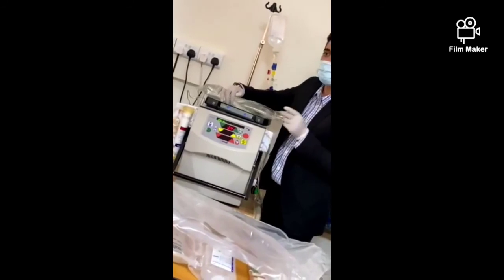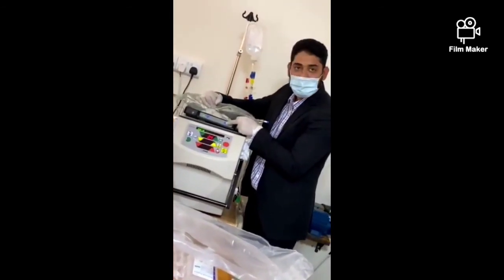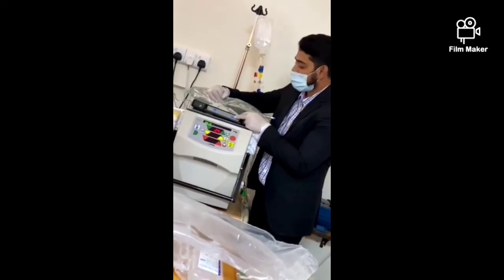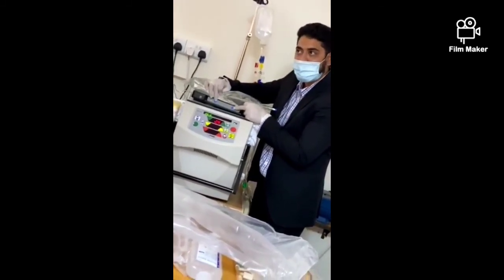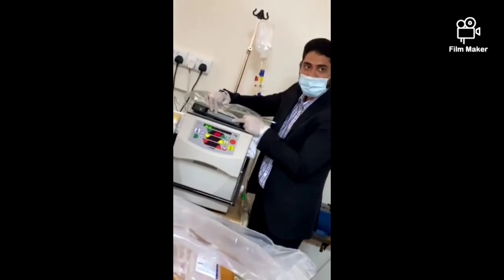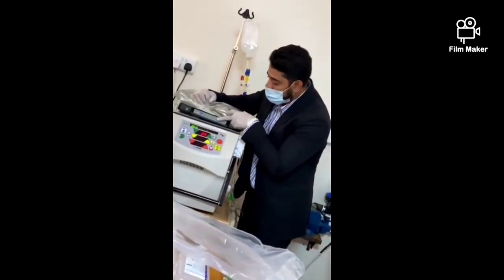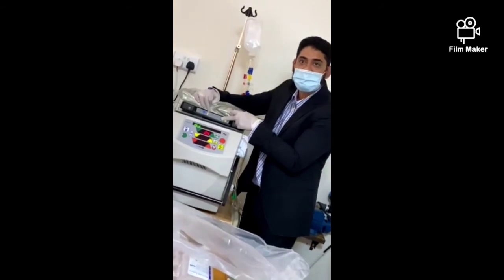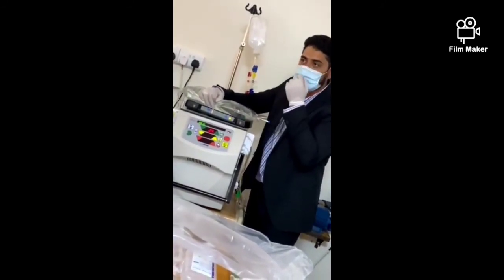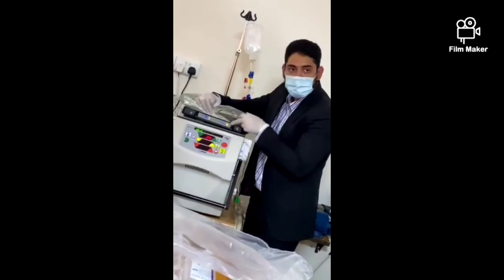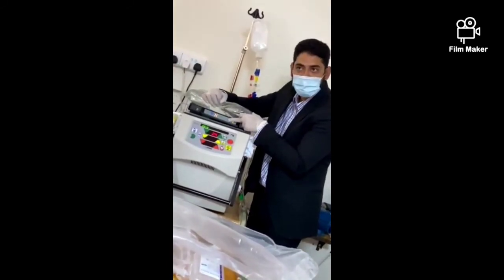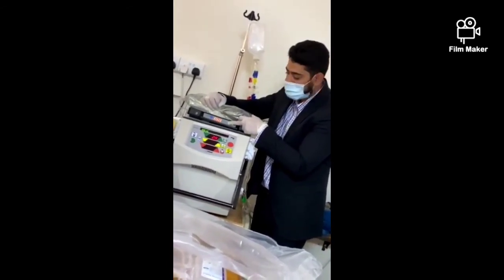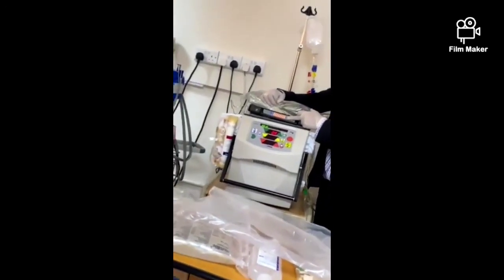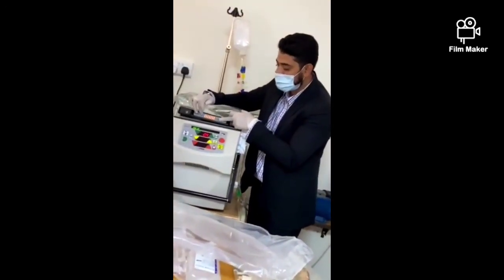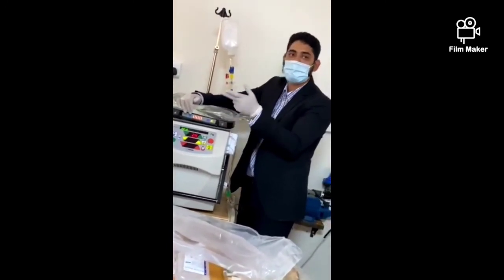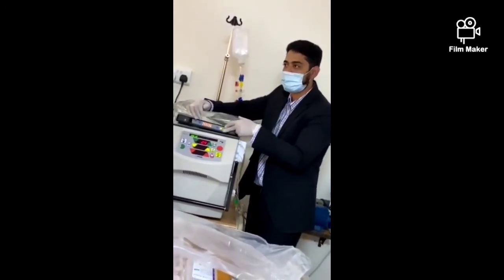Okay. Now if you need to increase the temperature, how will you increase? There is only the minimum and maximum temperature. Yes. So you see now, when I put this one, light comes. This is 31 degrees. It will start from 30, so 31, and if you make again 32, 33, 34, 35, 36, 37, 38. Maximum 38. So we recommend 36. But if some patient feels cold, you can increase to 38 also, no problem.